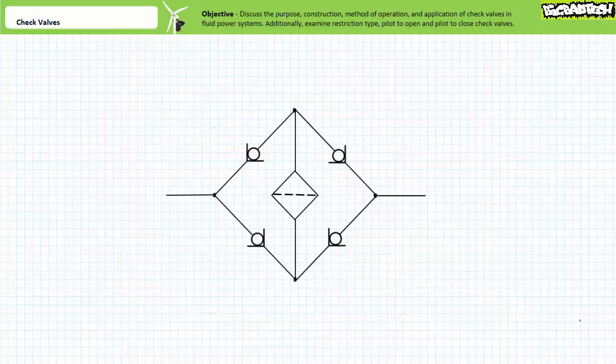Consider four check valves in a special arrangement that ensures the unidirectional flow of fluid through a filter in a system characterized by bidirectional flow. As we'll later learn, filters are fluid conditioning tools ordinarily meant to be run in one direction only.